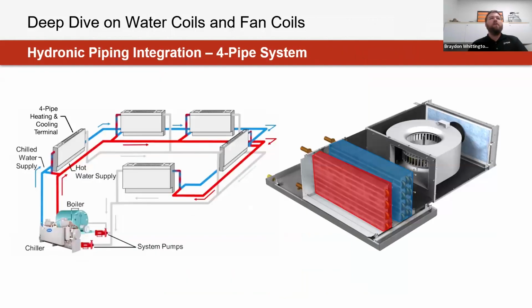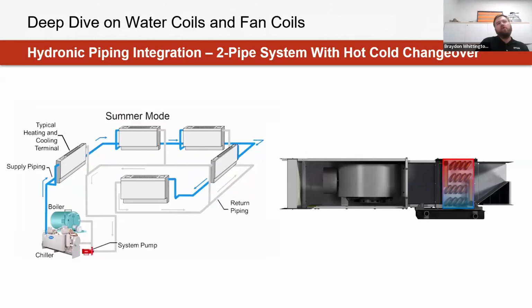In terms of different approaches to piping configurations, one configuration we'd see, and this is an example of a reheat configuration for 4-pipe, essentially has heating and cooling supplies run through the same equipment, depending on the time of year and what the building needs. But one very common approach, instead of having additional valves in the system for this form of changeover, for equipment like these trench heaters on screen or these window sill commodity vertical units, is 2-pipe changeover systems. So instead, one individual coil operates in summer mode as well as heating mode for wintertime as things start to get cooler.